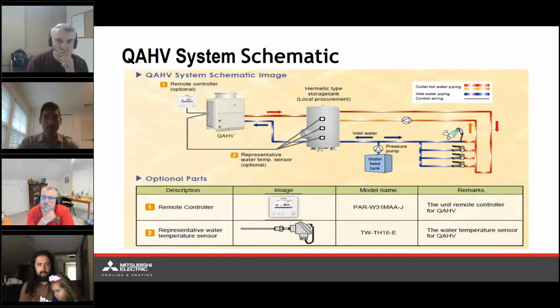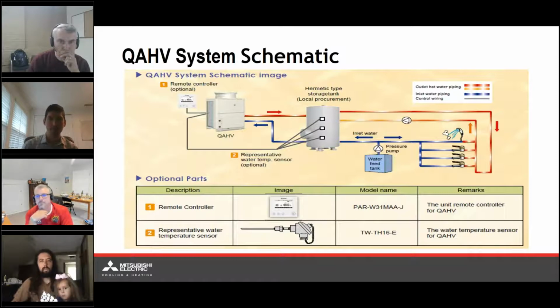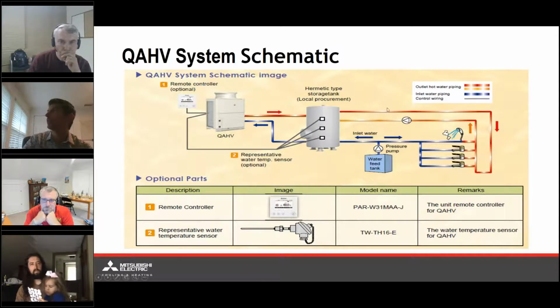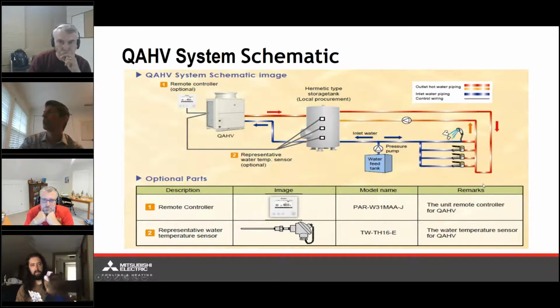Now, in this particular example, we have up to 3 thermistors in one storage tank, so that way we can detect and see the stratification of the water in the water tank. So the typical primary storage tank feeds to a temperature maintenance storage tank. That's what we're talking about for this particular scenario. And just to showcase a little bit further, in this example, we have multiple sinks, a shower system as well. So this is for an entire building's hot water demands, is what we're looking at here.